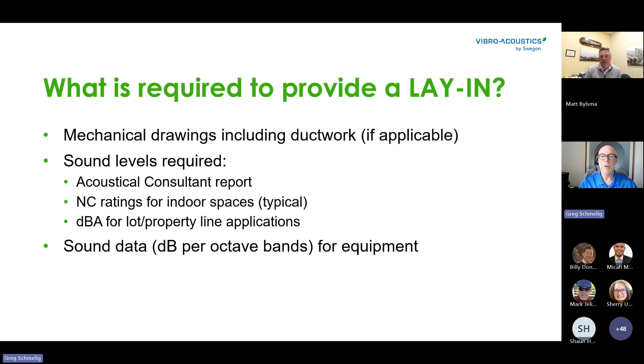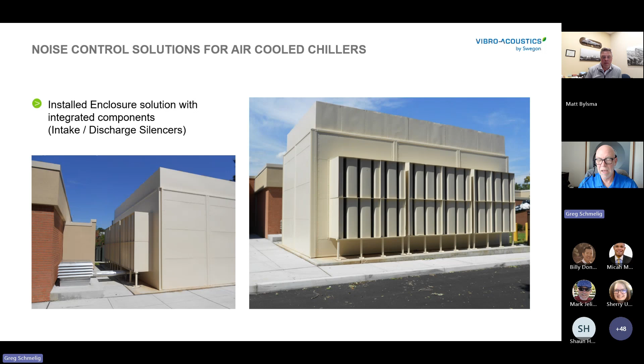Here's an example of an air-cooled chiller where we had to attenuate right at the system itself. We built an enclosure with intake and discharge silencers at very minimal pressure drop, in some cases less than 0.10 inches of static pressure, because those fans can't handle any dramatic increase in pressure drop.